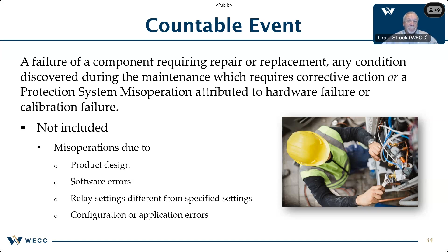Okay, let's discuss what a countable event is. A countable event is a failure of a component requiring repair or replacement, any condition discovered during the maintenance which requires corrective action, or a protection system misoperation that's attributed to hardware or calibration failure. Misoperations due to product design, software errors, relay settings that are set from different specifications, or configuration or application errors are excluded. Next, please.